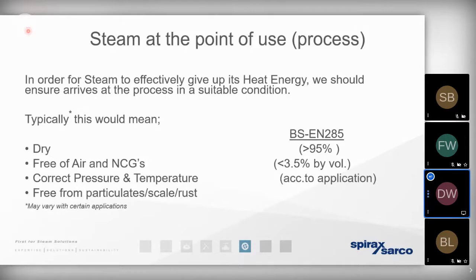But for certain processes, especially where steam is going to be used for direct injection purposes, for example, in the food, beverage, pharmaceutical, fine chemical sector, we don't want to be contaminating an atmosphere or a product with excess moisture, excess water. And that water is going to be chemically conditioned as well. So we could be causing a point of contamination. So we know there's a benefit in keeping the steam dry. So not just are we removing the risk of contamination there, but it also means that the drier the steam, the more energy there is contained within the steam.